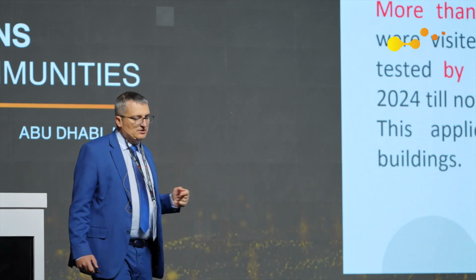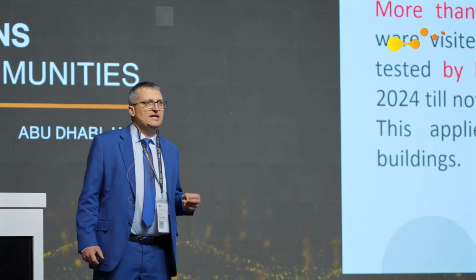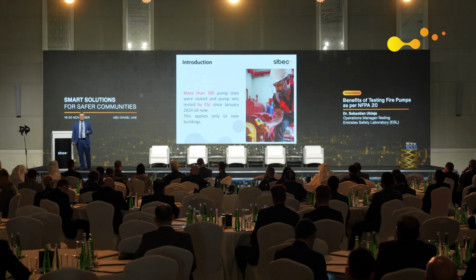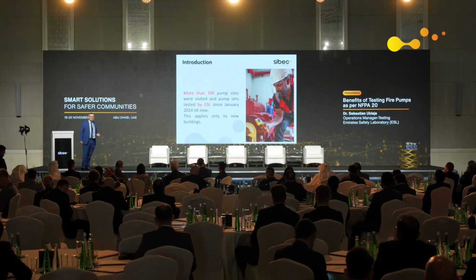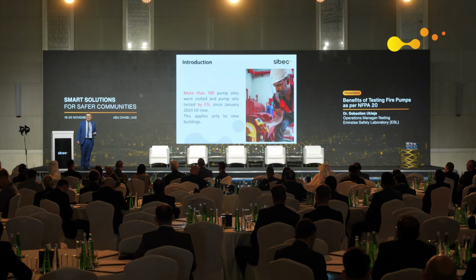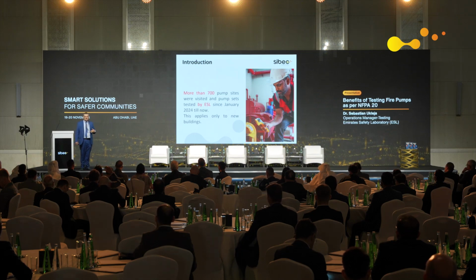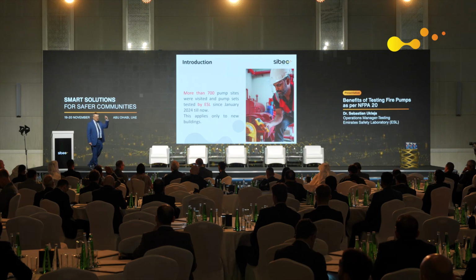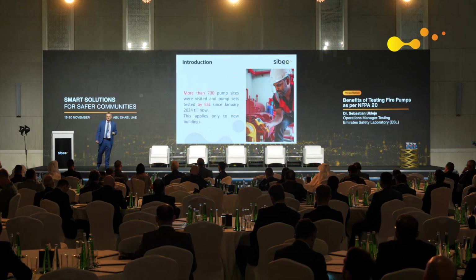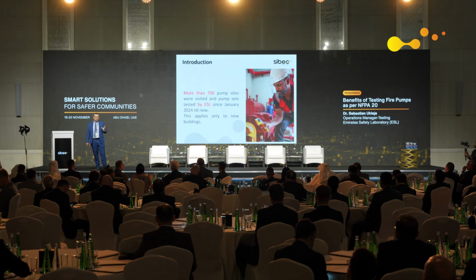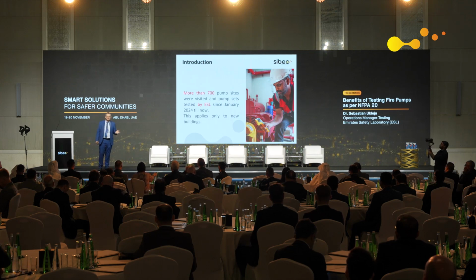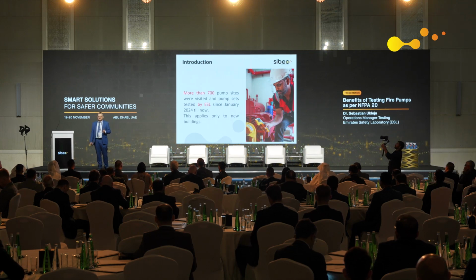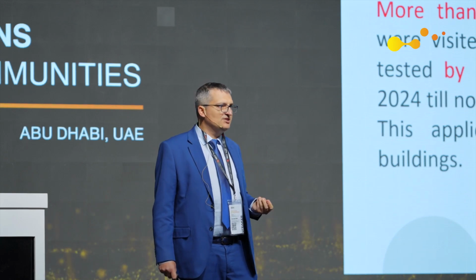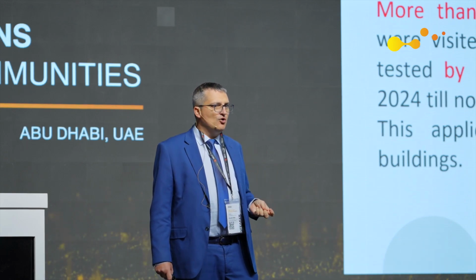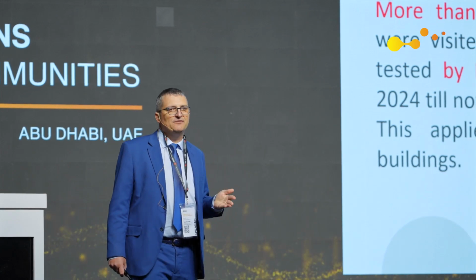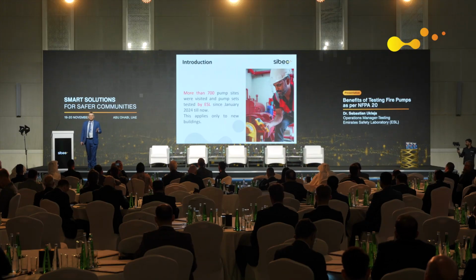We as ESL - I'll come back to the checklist in a second - we are located in Dubai, and since January 2024, for almost the last two years, we've tested more than 700 installations. Some towers had several sets of pumps depending on height, so it was like 700-plus projects. Based on that almost two years of experience, I wanted to show you why initial testing of systems is crucial, and what can go wrong that leads to a situation where, in the event of a fire, a new fire pump will not work.